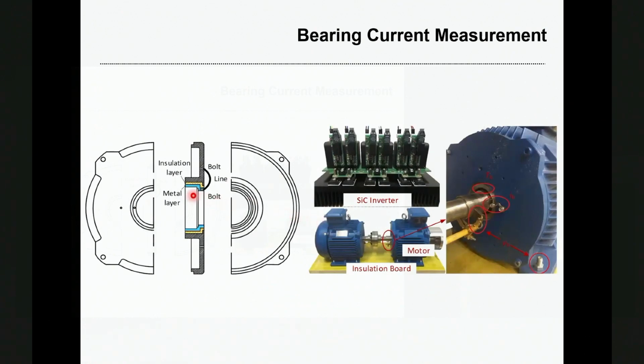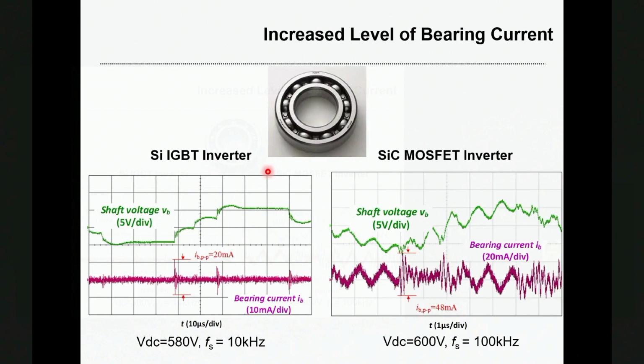And we can set up a system to measure the bearing current by bypassing the current originally going through the bearing. Now we can force the current to go through another wire, and then we can measure the bearing current here. And here is a comparison between a silicon IGBT based inverter and a silicon carbide MOSFET inverter for the bearing current. As you can see, with a silicon carbide MOSFET inverter with much higher switching frequency and switching speed, the bearing current is much higher than the silicon IGBT based converter.